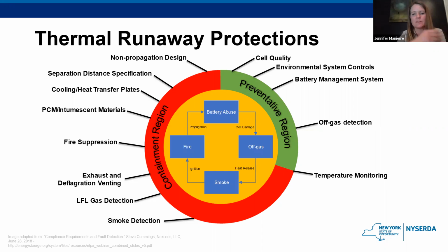And then as you work your way around the circle, we're progressing to backups to the backups, right? So God forbid that the battery management system is not able to isolate that abused battery in time, and it does begin to off-gas. You have off-gas detection in place to notify someone that that is happening. From there, maybe temperature monitoring. If it continues to increase in temperature, you want alarms to go off and some way of dealing with that. Smoke detection, lower flammability limit for gas detection.